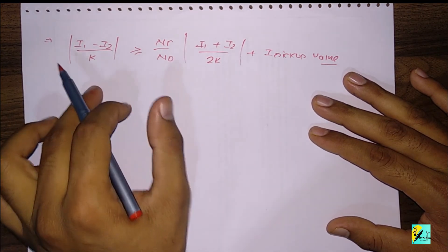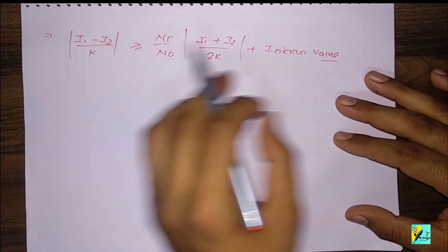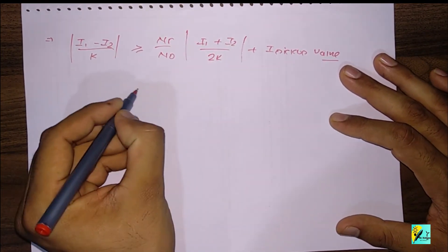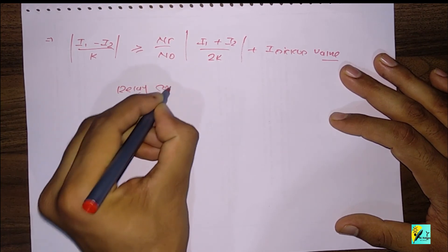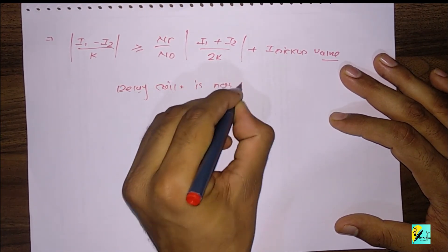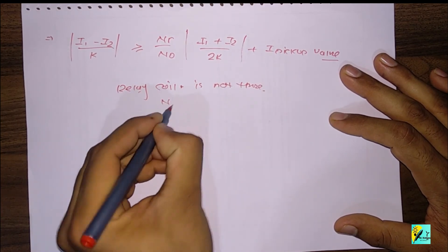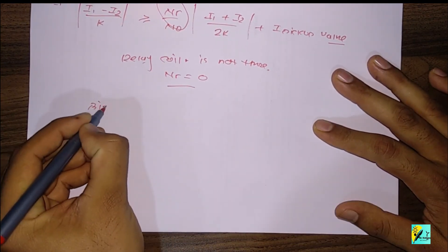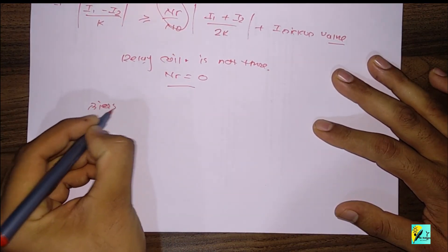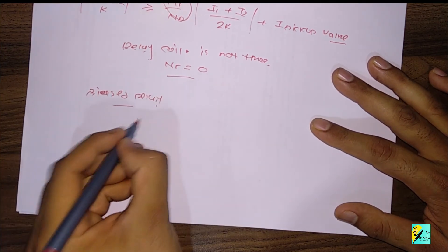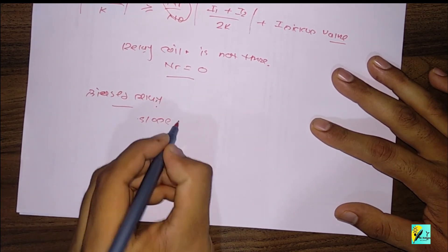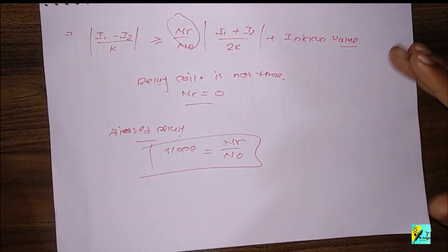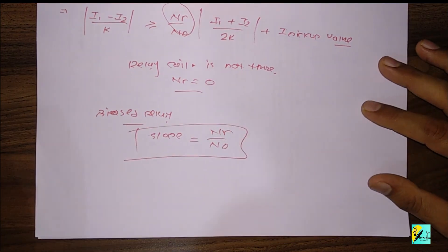The equivalent operating coil current should be more than the equivalent restraining coil current plus the pickup value. If the restraining coil is not there, you consider Nr equal to zero, and you get the earlier simple differential relay condition.